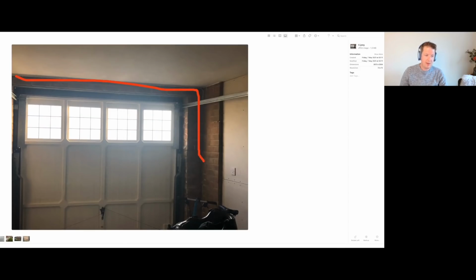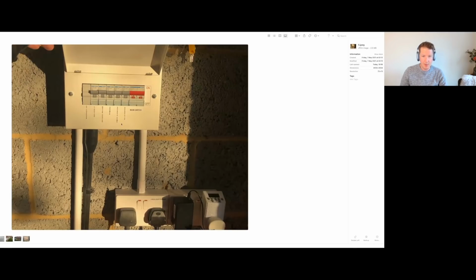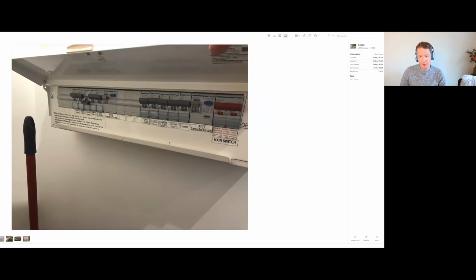But there are a few other things that we need to consider here, because obviously we mentioned we've got quite a high load on this garage. So it's going to be running, you know, maximum demand is probably about 40 amps realistically from the garage itself. Then we've got house circuits here, kitchen sockets. You could be running a dishwasher, washing machine, tumble dryer, ground floor sockets, all the various appliances that are plugged in. And then you've got lighting, you know, central heating. All of these things add up. So the maximum demand for the property is quite easily above 60 amps.